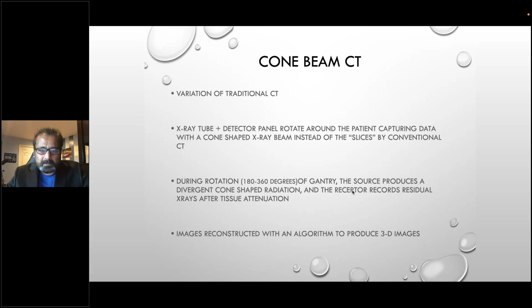The conventional slicing CT has better resolution than cone beam CT, but the radiation dose is substantially reduced in the cone beam CT. We already talked about augmented fluoroscopy, but there are tomosynthetic algorithms now in augmented fluoroscopy that give you a reasonable picture, compared to that of cone beam CT. Sometimes those images are comparable in well manufactured devices. I'm not going to mention any names here, but there are some augmented fluoroscopy images that are comparable to cone beam CT images and much cheaper.